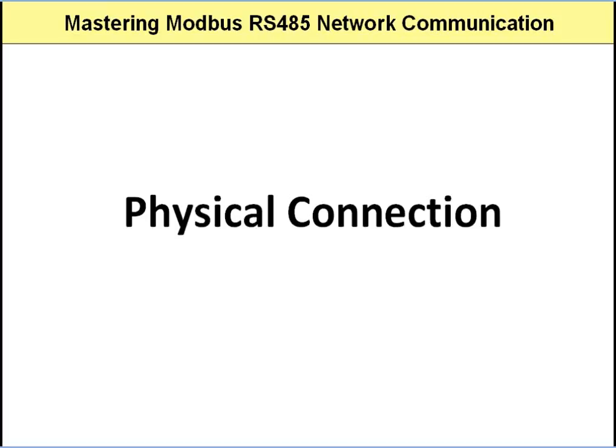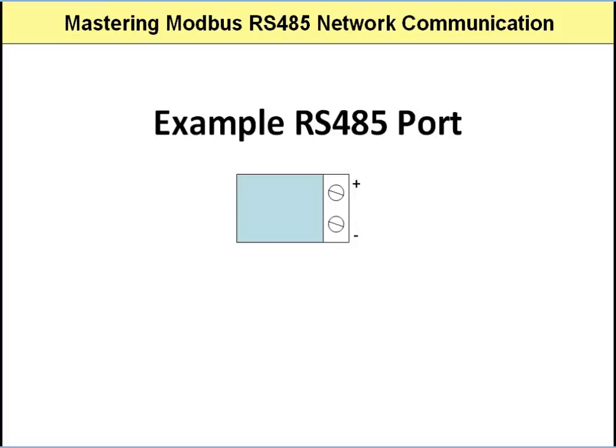On any device that supports RS-485, there must be a physical RS-485 communications port. Though this port may be housed in various types of connectors, more often than not you will see it as two screw terminals. One of the screw terminals will be marked positive and one will be marked negative. RS-485 uses only these two lines for connection.